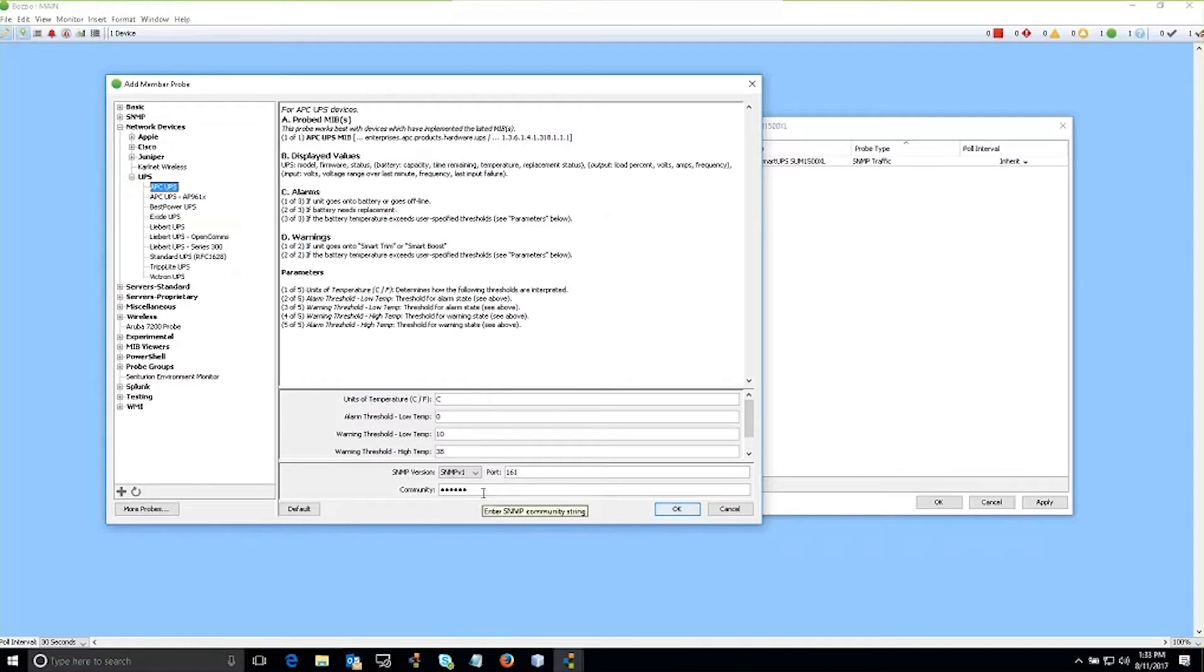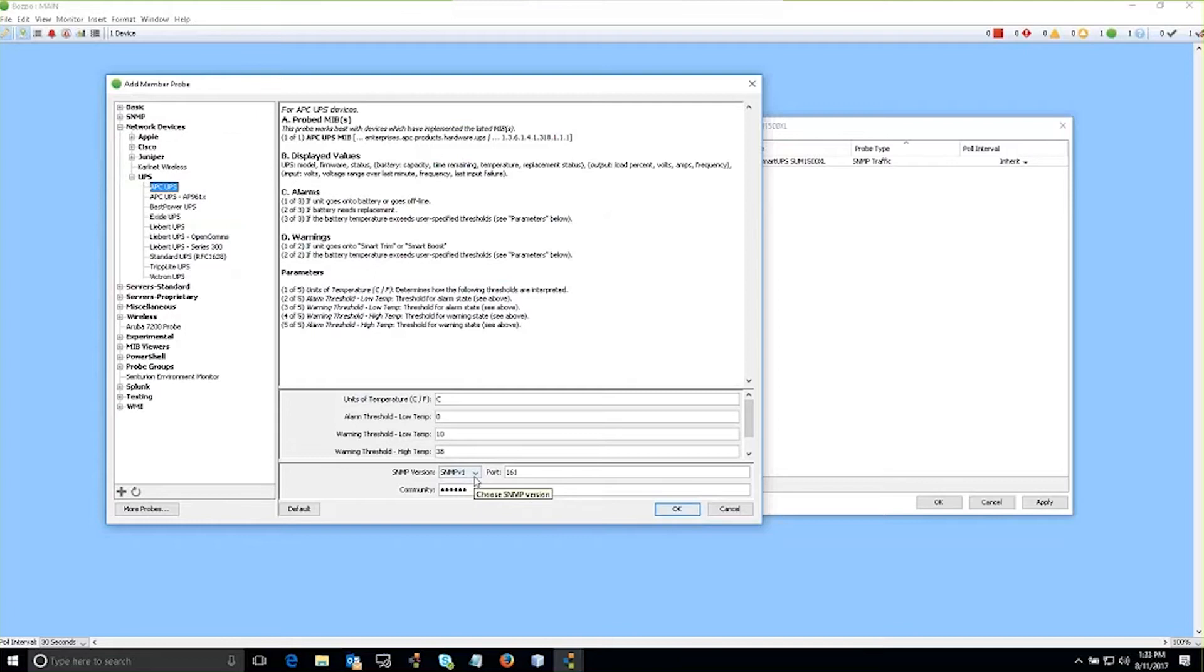We support all versions of SNMP. So if your device speaks SNMP, we encourage you to configure SNMP so we can have a better response. Ensure that the SNMP version and string are consistent with what the probe is showing. By default, we present version one with a string of public.